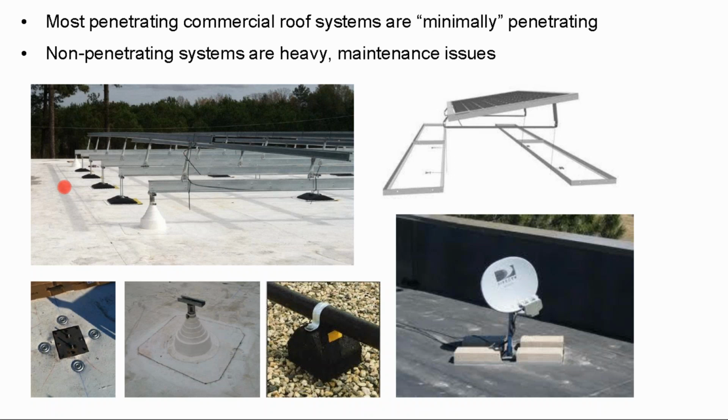But if the roof is relatively strong, the question becomes, well, how much weight does a commercial solar array add to the rooftop? And these concrete-based systems that fill in the whole ballast pan with concrete can weigh 10 pounds a square foot or more. And there's a lot of buildings where, once you start talking about adding an additional 10 pounds per square foot to the rooftop, the structural engineer says, no, there's not enough headroom built into that to stay within our safety factors.